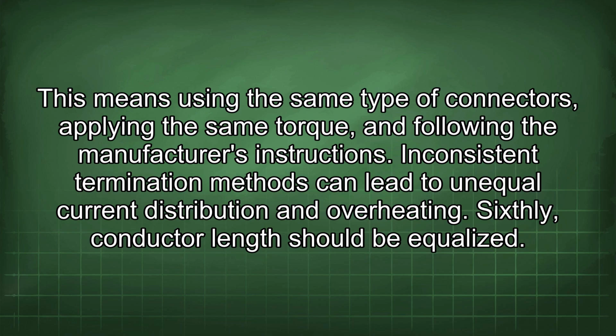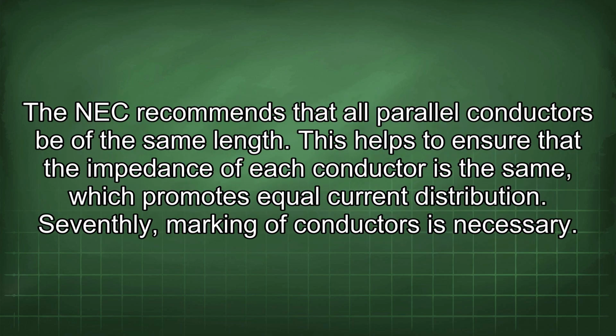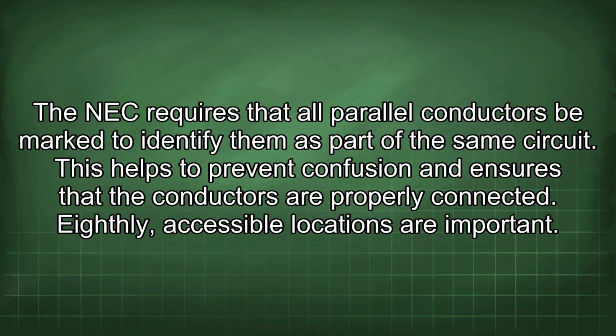Sixthly, conductor length should be equalized. The NEC recommends that all parallel conductors be of the same length. This helps to ensure that the impedance of each conductor is the same, which promotes equal current distribution. Seventhly, marking of conductors is necessary. The NEC requires that all parallel conductors be marked to identify them as part of the same circuit. This helps to prevent confusion and ensures that the conductors are properly connected.